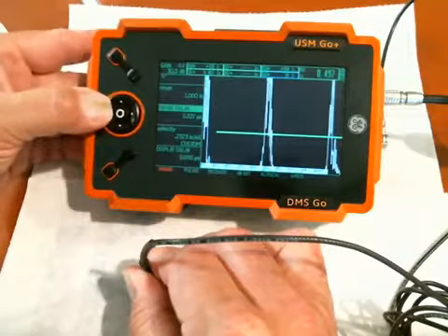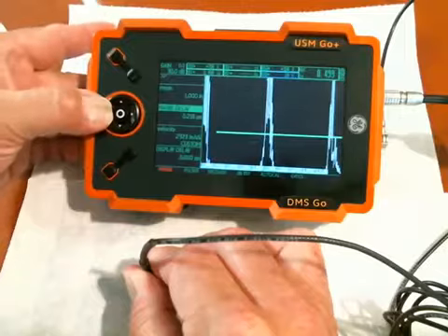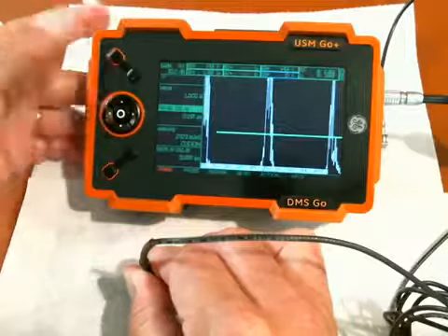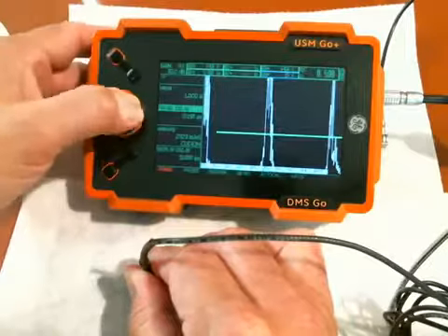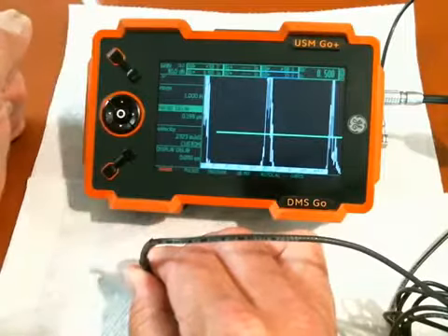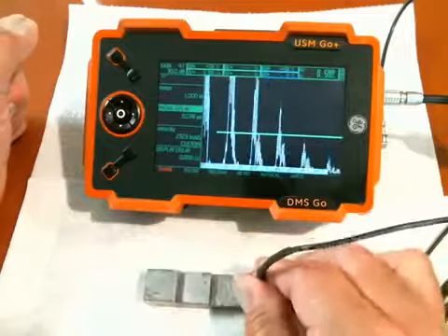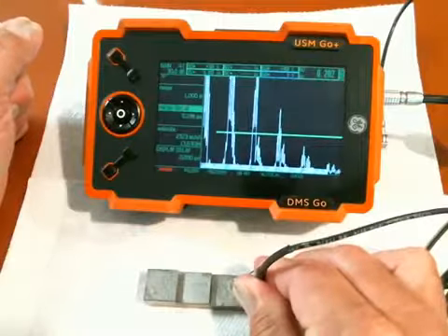until my thickness comes down to 1/2 inch. Okay, so at 0.197, 199 microseconds of probe delay, I have 1/2 inch. If I go to 0.2 inches, I'm measuring just a little bit thick.